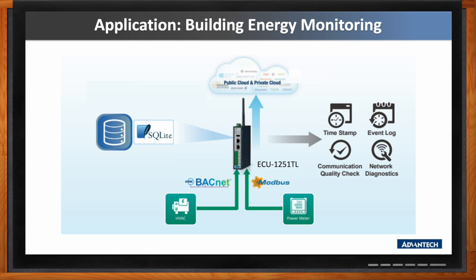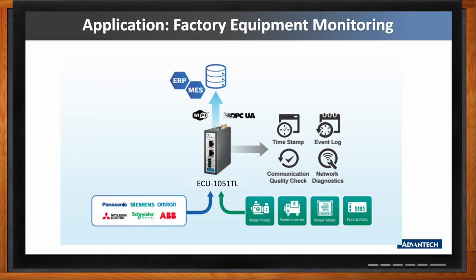Another application is equipment monitoring in the factory. In the factory, there are PLCs from different manufacturers like Siemens, Allen-Bradley, and Rockwell, making it hard to collect all information from those different PLC manufacturers. To collect and integrate the PLC information, the ECU-1051 reads the PLC I/O registers with drivers and then converts it into OPC UA protocol, which is supported by MES and ERP systems. The data from the PLC can link to ERP and MES systems via OPC UA through the gateway. To avoid complicated wiring, a Wi-Fi accessory is added for wireless communication.